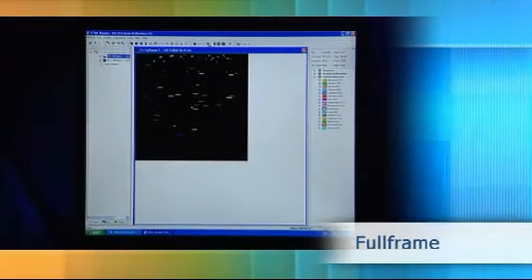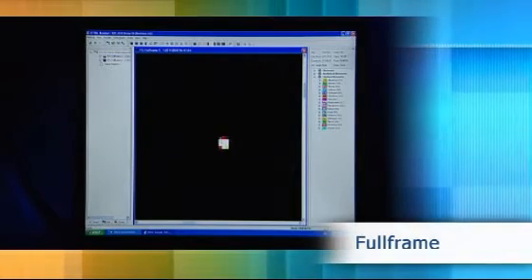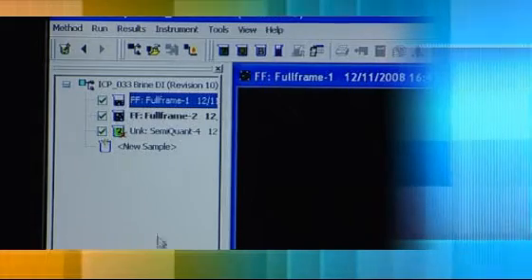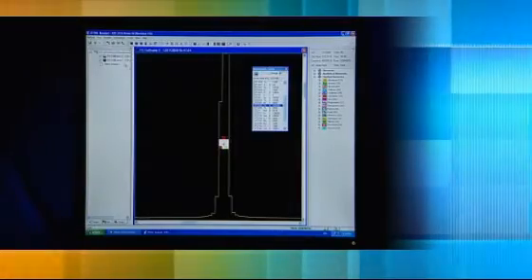Full frame allows qualitative compositional analysis of a sample, semi-quantitative analysis of lines that have not been calibrated, and enables the subtraction of one full frame from another, revealing the presence of contaminants in samples.